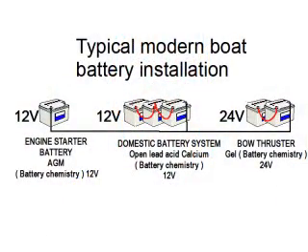A good practical marine example is an AGM battery bank for your starter battery, an open lead acid battery bank for a domestic battery bank, and a 24V gel battery bank for the bow thruster or anchor winch — which is a much better option than a 12V version. This causes a problem for most multiple standard output battery chargers as they can only be set to one battery chemistry type and one voltage.